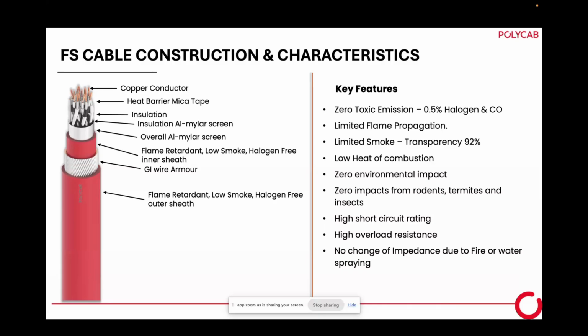Because if you see, aluminum has a melting point of 600 degrees centigrade. When the fire goes to 900 degrees temperature, the aluminum conductor melts. So there is no question of circuit integrity. Okay, coming to the construction. The conductor is copper. Over the copper, we apply one heat barrier, mica tape. So here it is very important, the mica tape application, the heat barrier. Over that there is an insulation as per normal electrical cable construction.